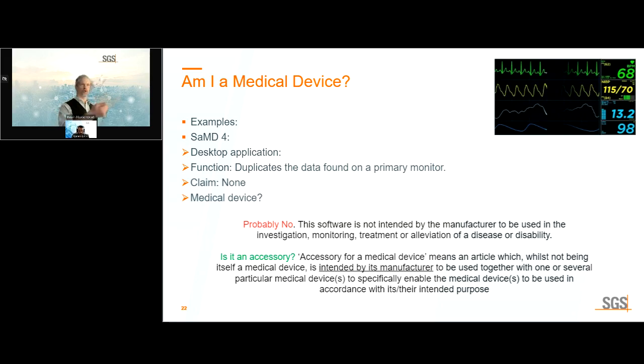And you plug your RF generators, microwave generators, X-ray generators into it. Something that's just a power station and a stand. If it's a commercial off the shelf, the answer is that that is an accessory, which is not a medical device. It is not intended by its manufacturer to be used with medical devices. If that same legal manufacturer places it on the market and intends it to be used with their devices for that purpose, now it's a medical device and therefore an accessory.